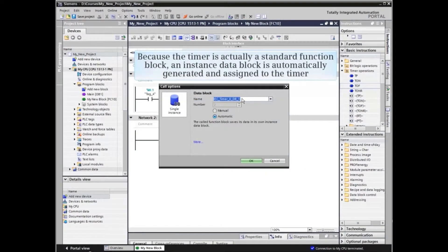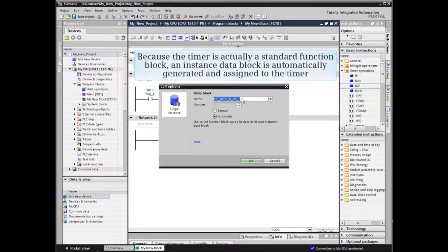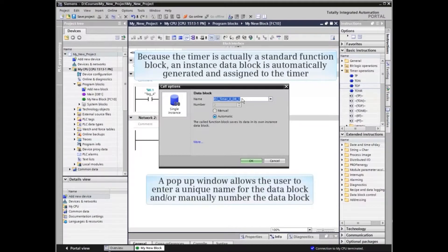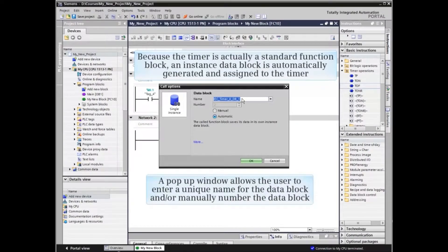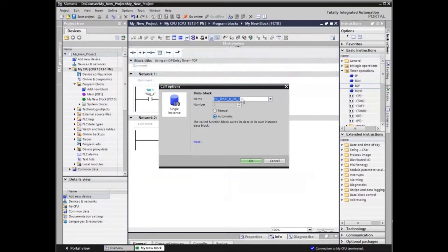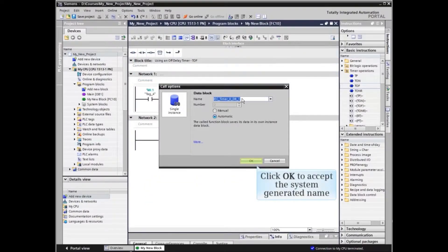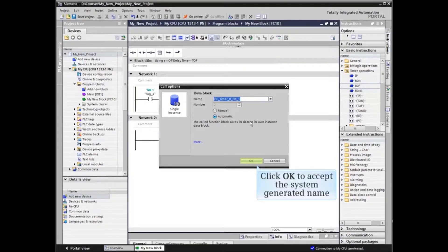Because the timer is actually a standard function block, an instance data block is automatically generated and assigned to the timer. A pop-up window allows the user to enter a unique name for the data block and/or manually number the data block. You can also accept the system generated name or number as we will do in the example.